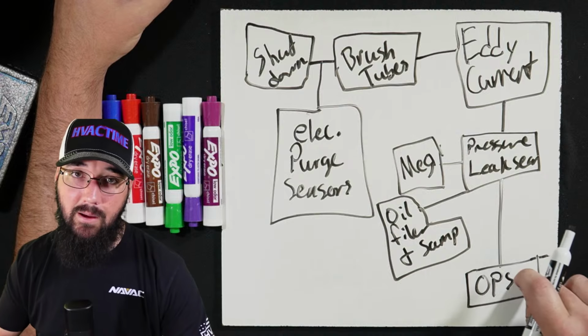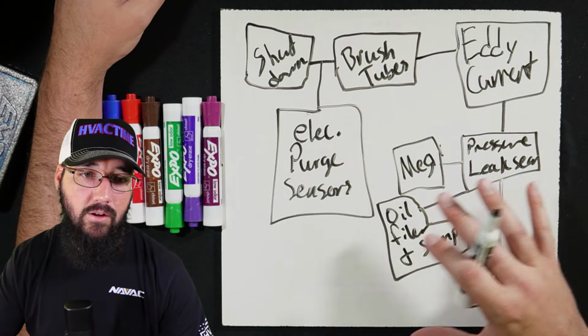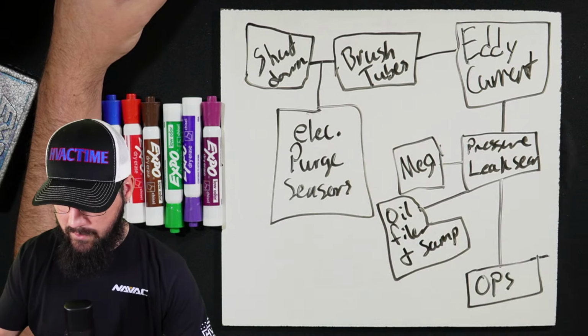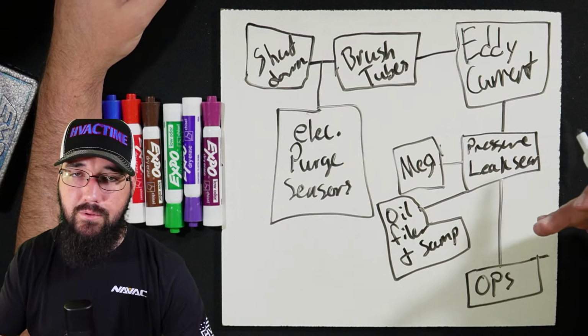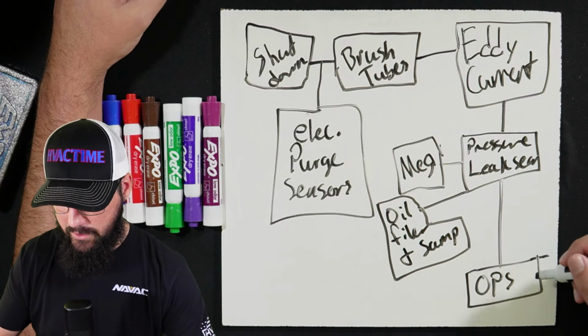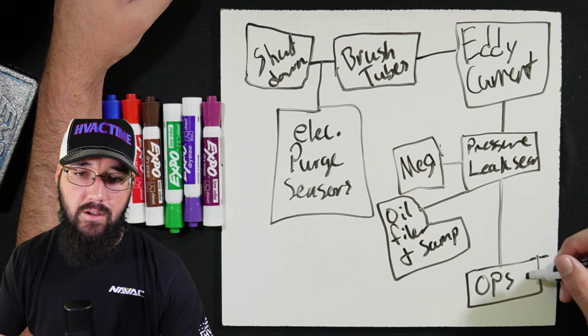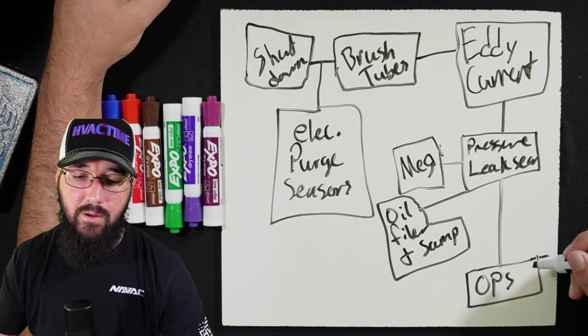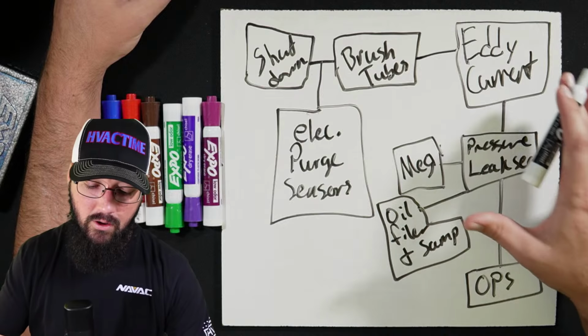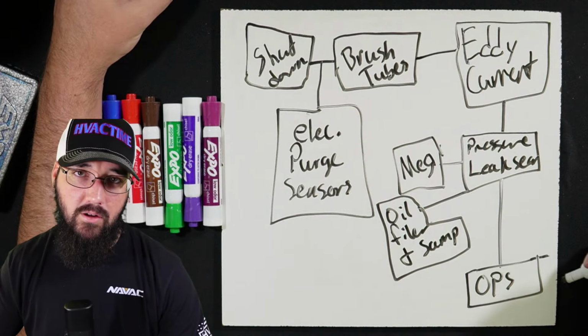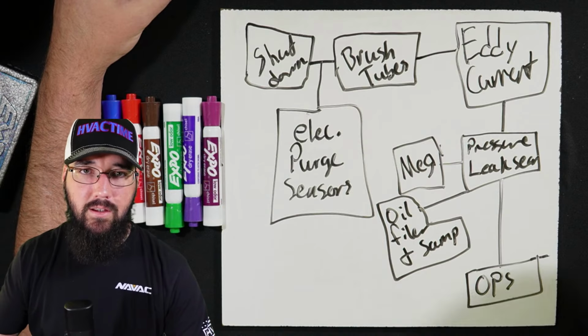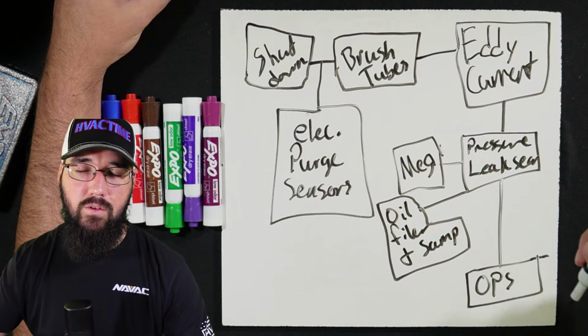By this time, I know that all my sensors are accurate. I know that everything electrically is good. I know where my refrigerant system conditions are, so I'm checking. This is where I'm logging the machine. It's the very last step of this process for me, doing a complete log. I want all this done before I go to log it, because I'm already there to do the service.